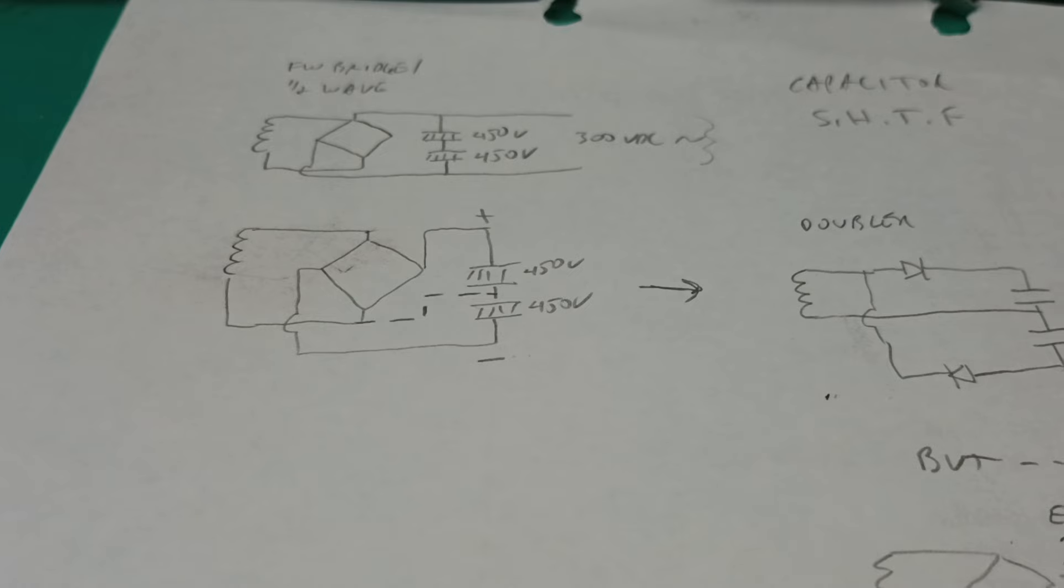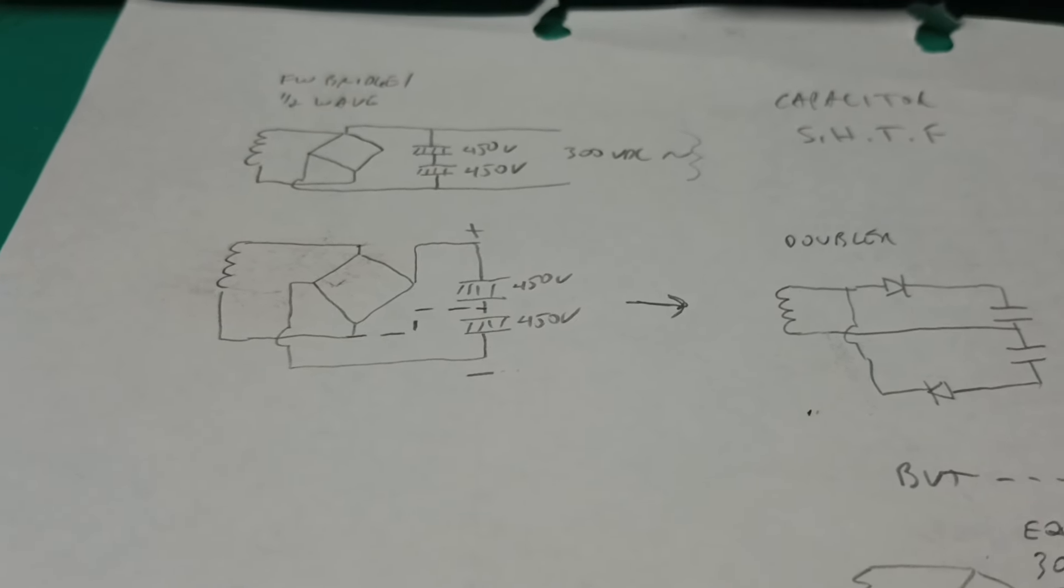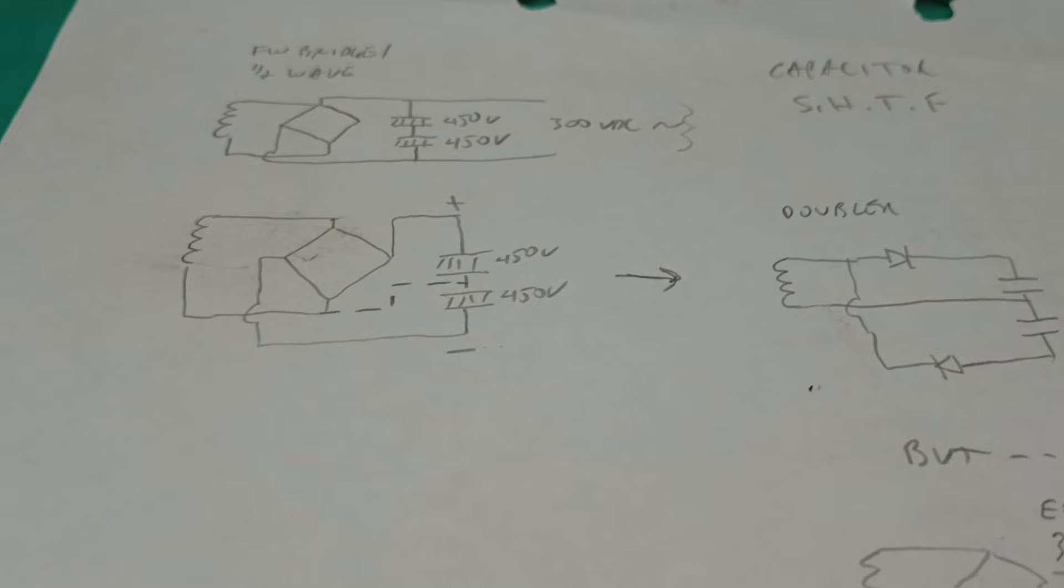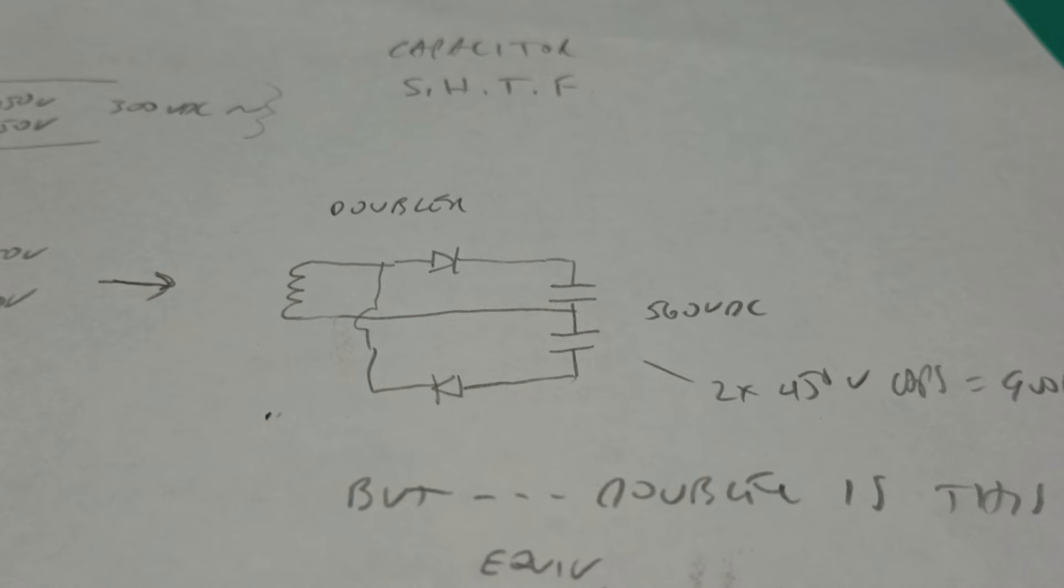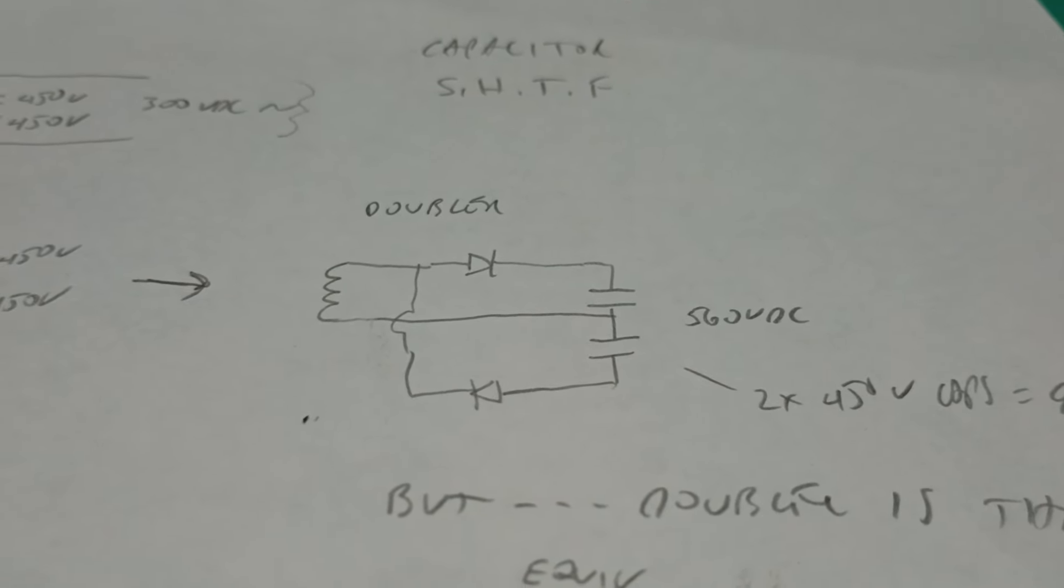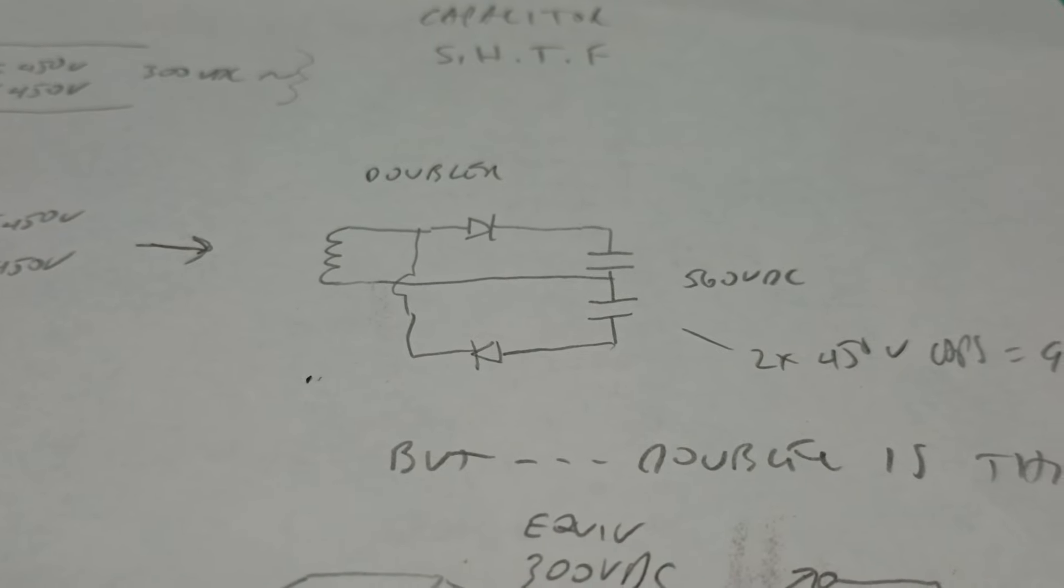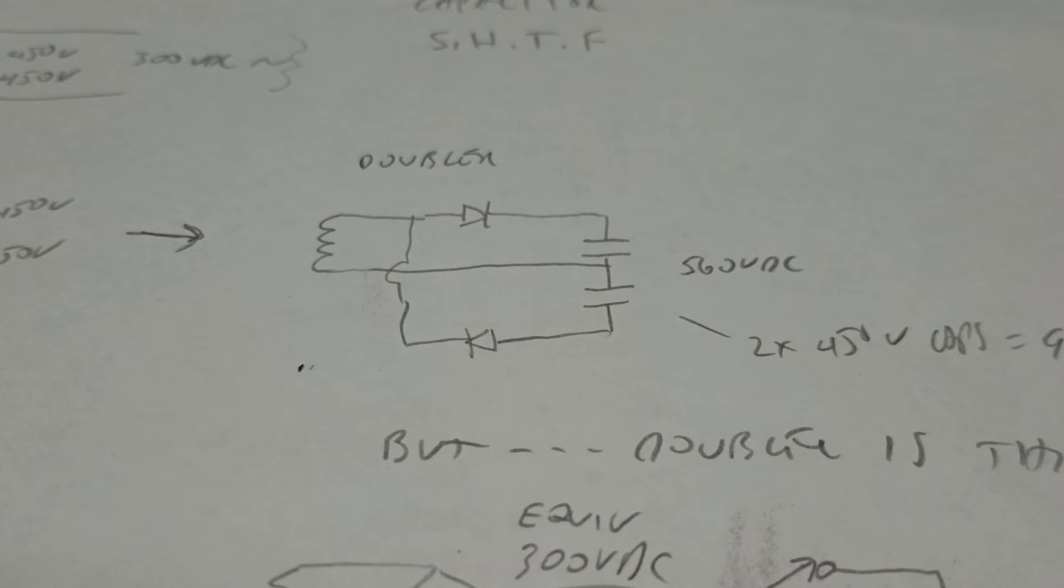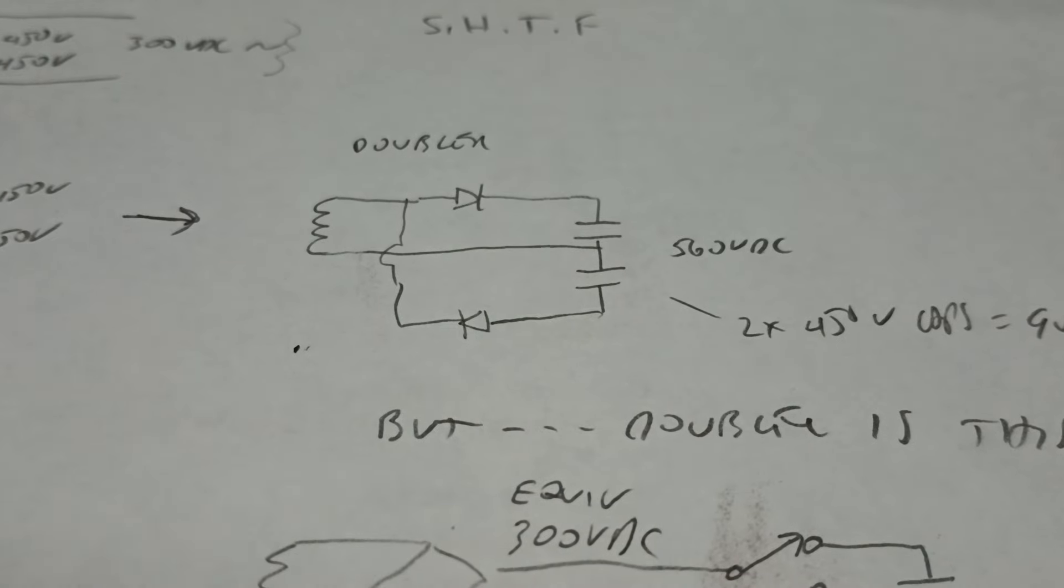Not only of not observing twice working voltage, but I actually exceeded, either met or exceeded, the working voltage for each capacitor. Well now, how can that do that? When the output is 560 volts DC, but the capacitors are good for 900? Well that still shouldn't be, that's going to shave some life off the other end, but there's no way that should bring failure in just a few minutes or an hour.